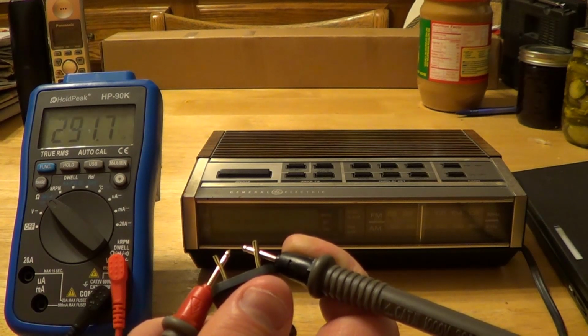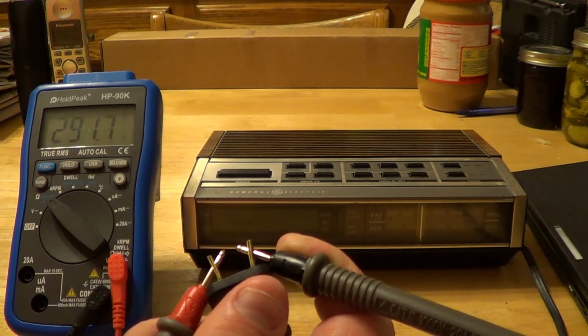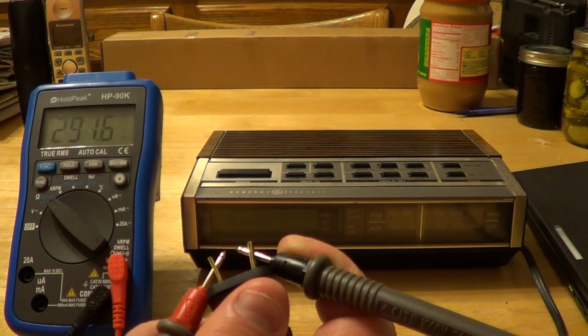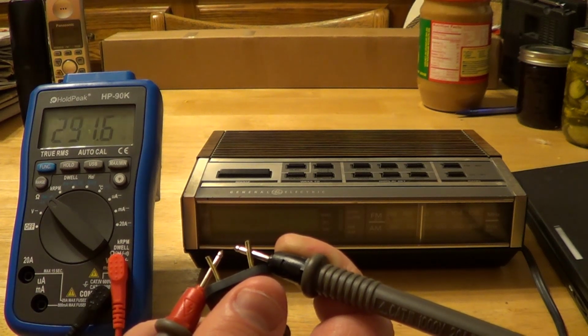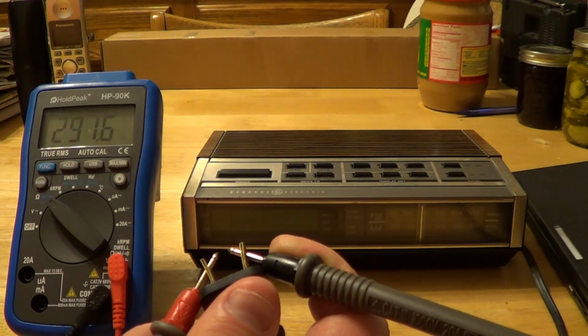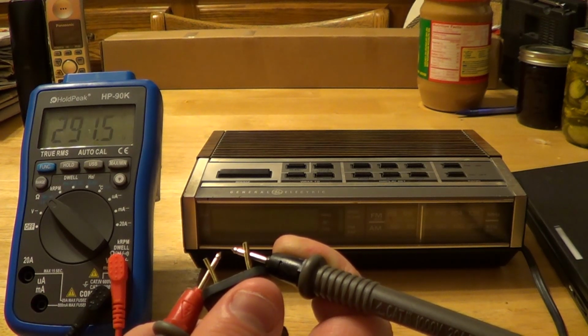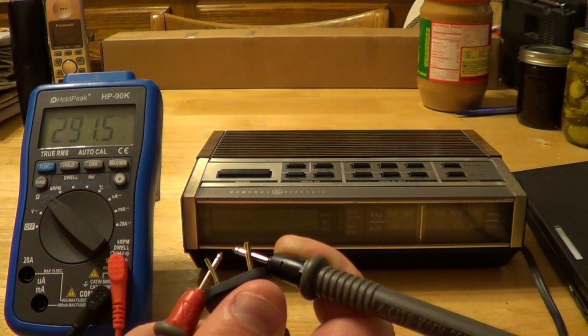Well, it's telling me that the cord set does have continuity. It's also telling me that the next thing in line, which is very probably the primary winding or line-connected winding of the power transformer, is not completely open and not completely shorted - it does have measurable resistance. Is it the correct amount of resistance? I don't know that for absolutely certain. I could use Ohm's law to figure that out, or I could just take an educated guess for right now, keep it simple, and say that transformer is probably okay.